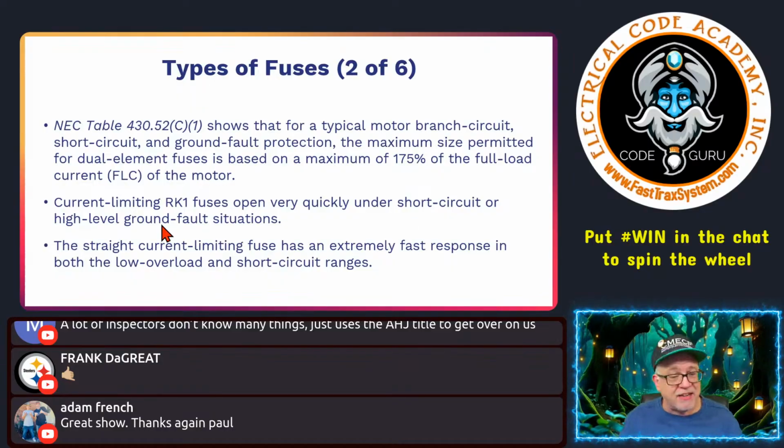Okay, and that may be a design professional. They may demand use of current limiting fuses in order to keep the level of current at a specific level for whatever piece of equipment or whatever they're doing. They may specify current limiting devices, okay? Now it says a straight current limiting fuse has an extremely fast response in both the low overload and short circuit ranges, okay?